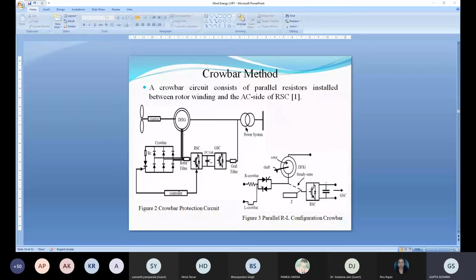With the crowbar circuit triggering, DFIG is transformed into, I have told that one, okay, when there is a fault, this DFIG is converted into the induction generator and it takes reactive power from the grid. So we will get the converters and rotor winding protected. Calculation or selection of crowbar resistance is very important, because we cannot take a high value of resistance or a low value of resistance.